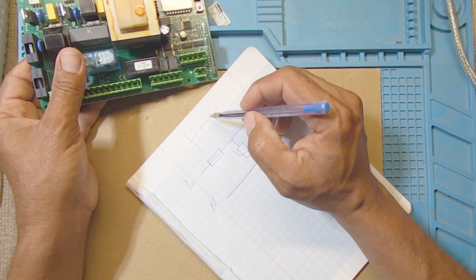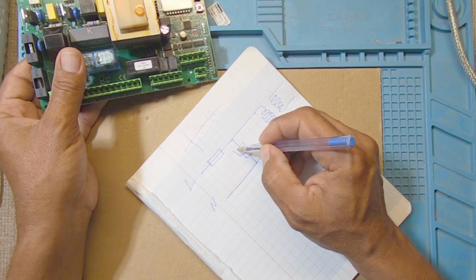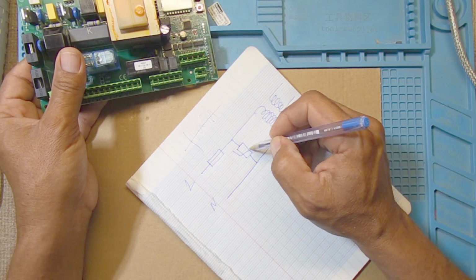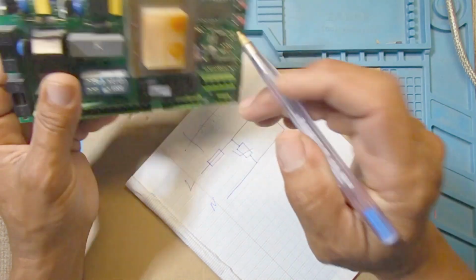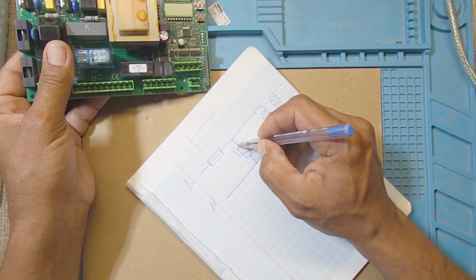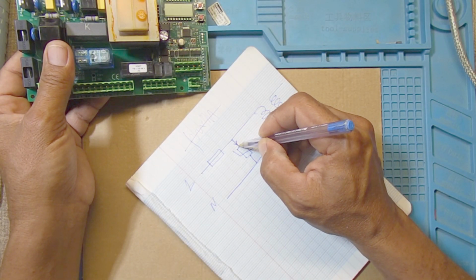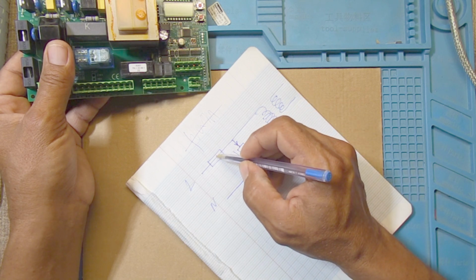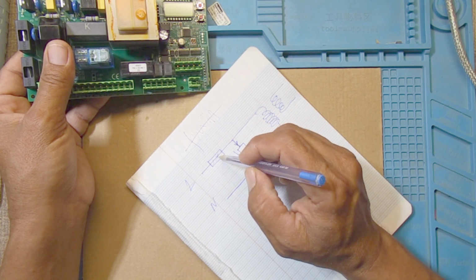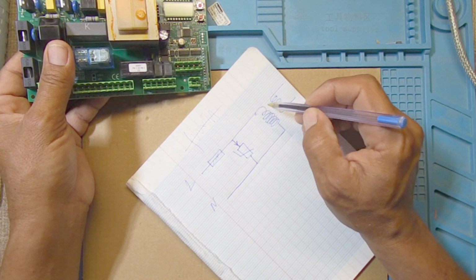If the voltage exceeds the maximum voltage of the varistor, it will become a short circuit. It will break, explode, and we have a huge current that will blow the fuse. When the fuse is blown, it saves the transformer.